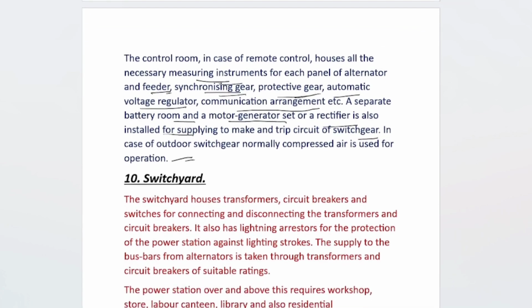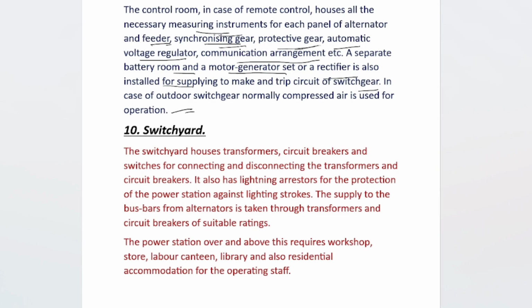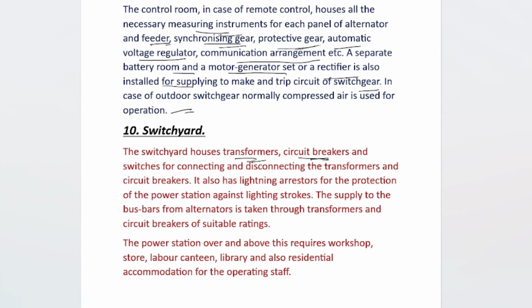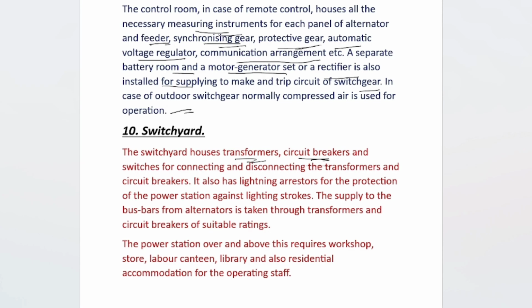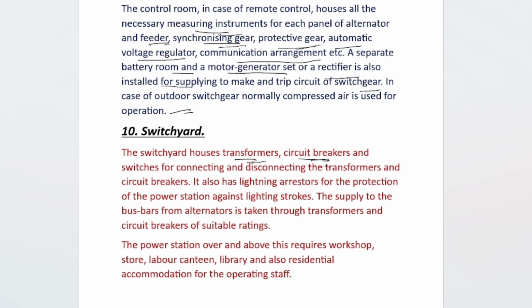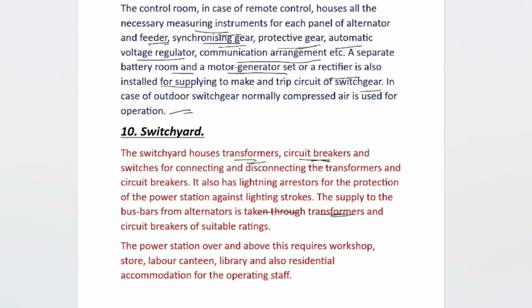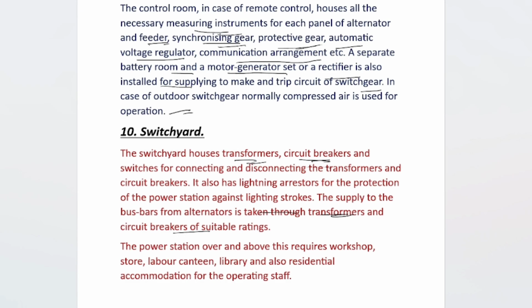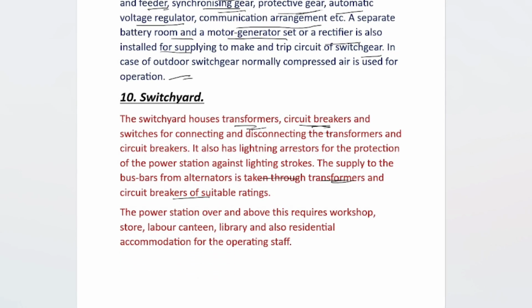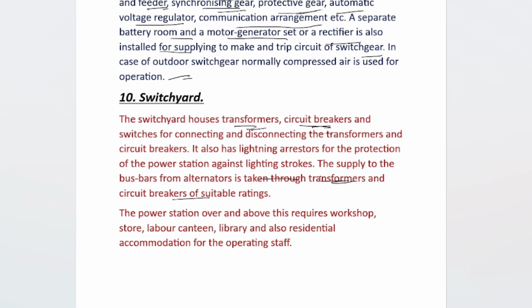Our next point is the switchyard. The switchyard houses transformers, circuit breakers, and switches for connecting and disconnecting the transformer and circuit breaker. It also has a lightning arrestor for the protection of the power station against lightning strokes. The supply to the bus bar from the alternator is taken through a transformer and circuit breaker of suitable ratings. The power station, over and above this, requires a workshop, store, labor, canteen, library, and also residential accommodation for the operating staff.